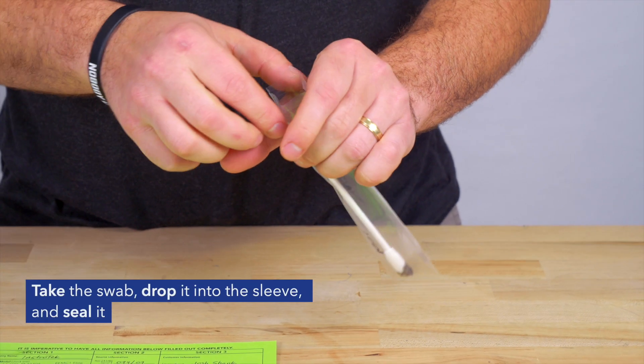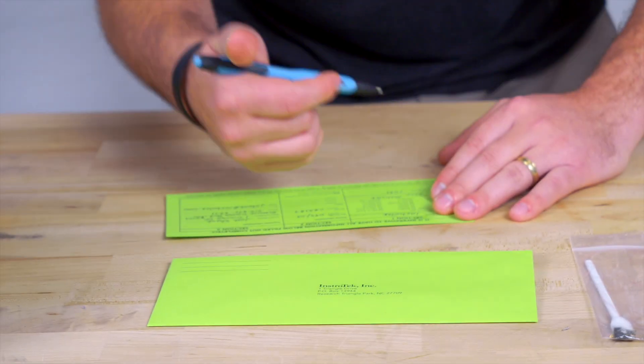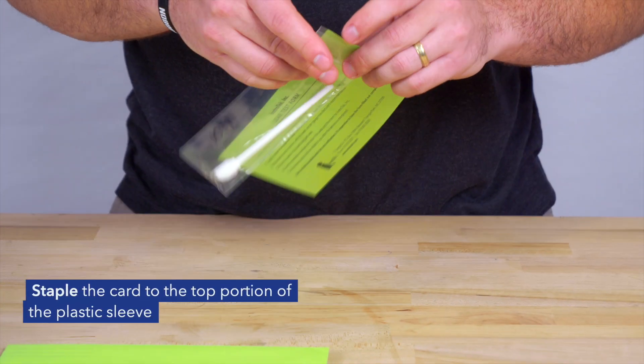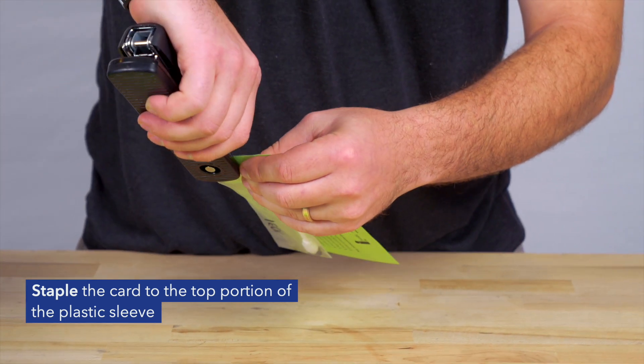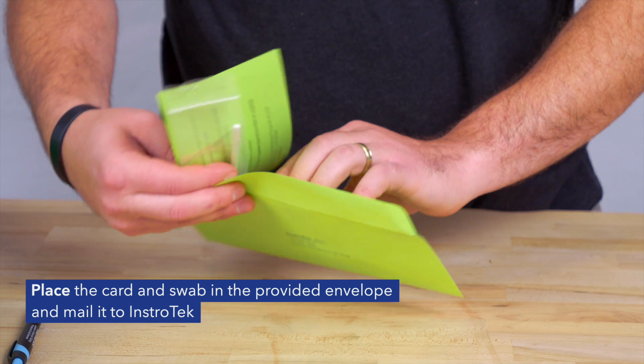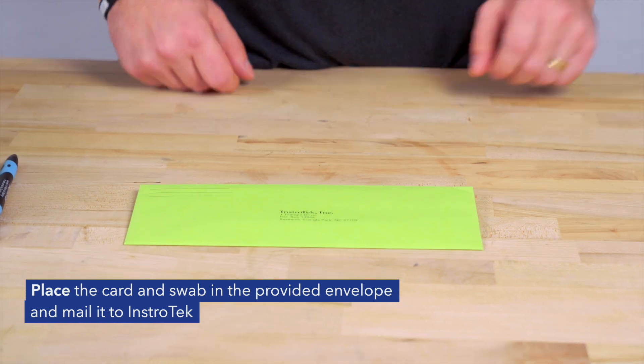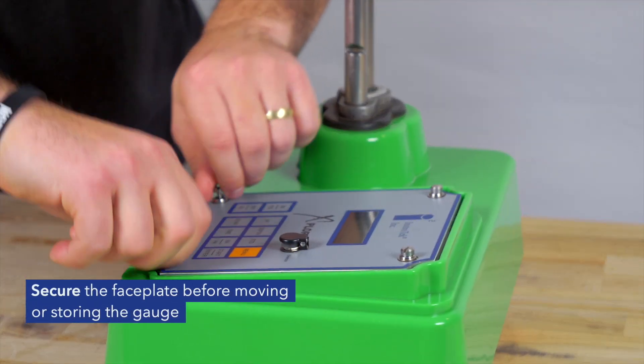Take the swab, drop it into the sleeve, and seal it. Sign and date the leak test card. Staple the card to the top portion of the plastic sleeve. Place the card and swab in the provided envelope and mail it to InstroTek. Secure the faceplate before moving or storing the gauge.